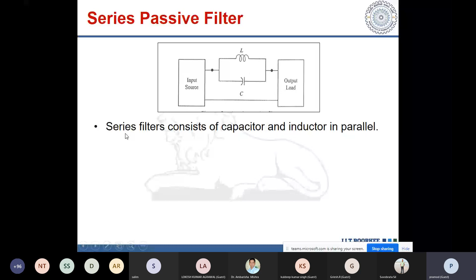It consists of a capacitor and inductor in parallel. Its purpose is to prevent a particular frequency from entering into the system, and it is basically used to block the third harmonic current. If you have a dominant third harmonic component, then to block it one may use a parallel tuned LC filter in series with the neutral wire, which will not allow the third harmonic current to flow.